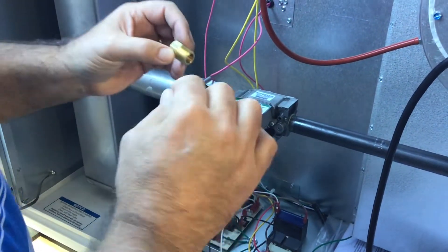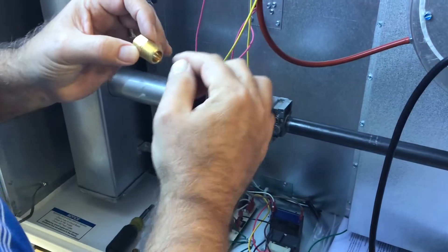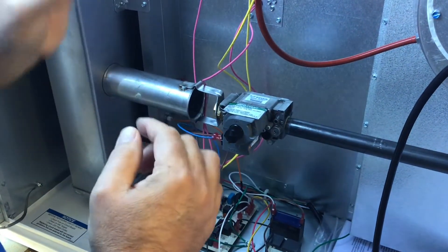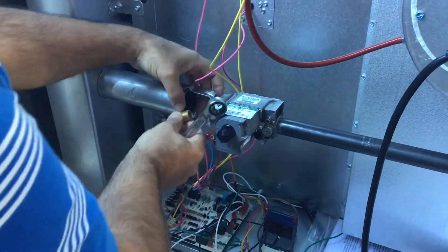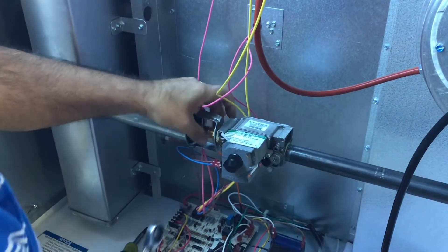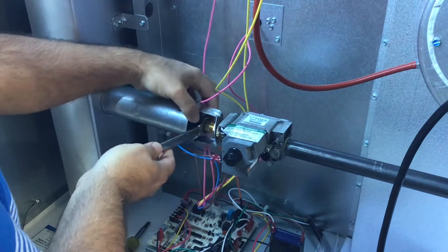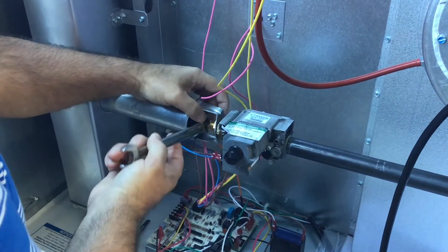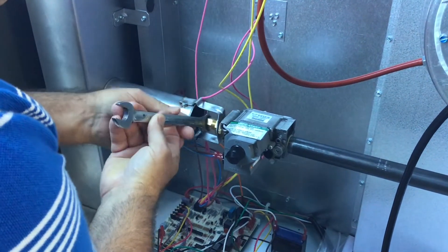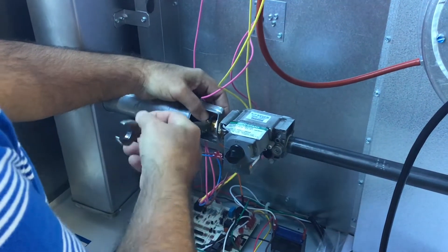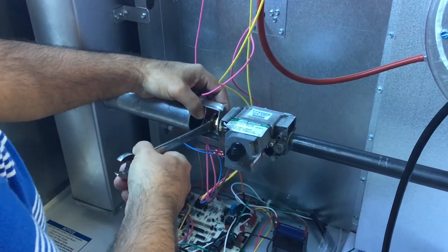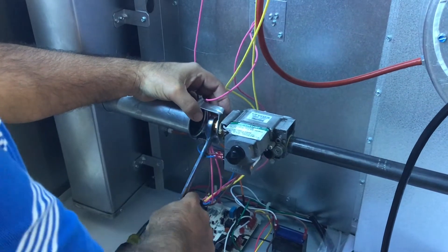For this period of instruction, we're going to put a little bit of pipe dope on the orifice, don't overdo it. We're going to tighten this until you feel it get snug and then go another quarter turn. That's all you need, you don't need to kill it.